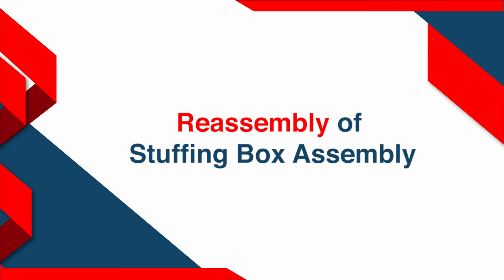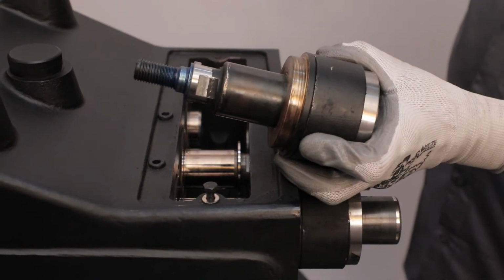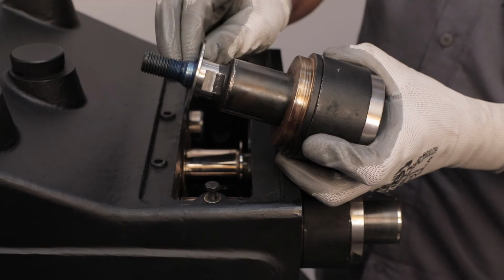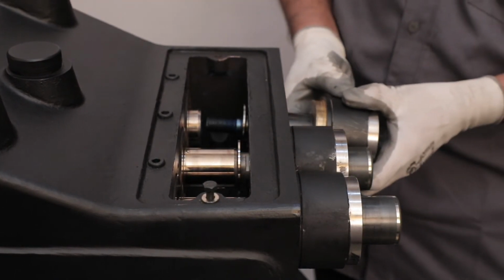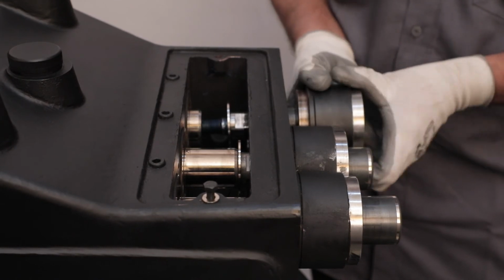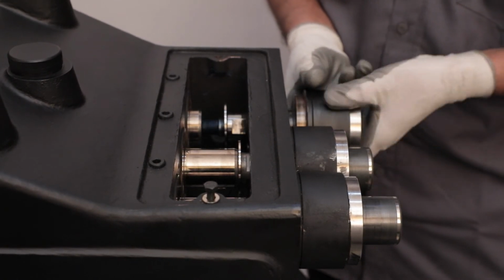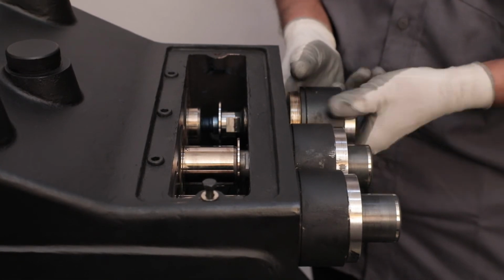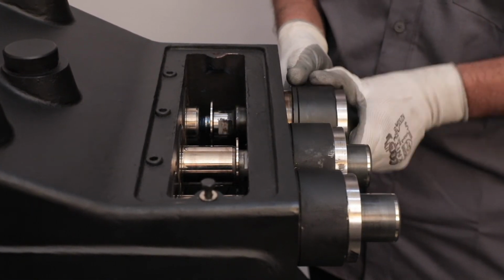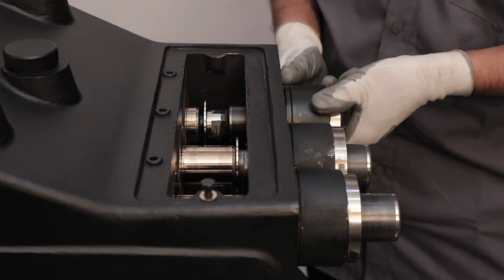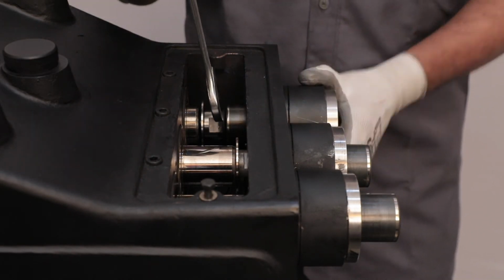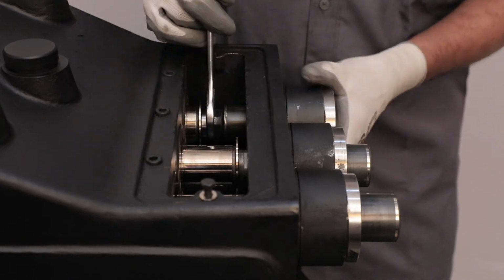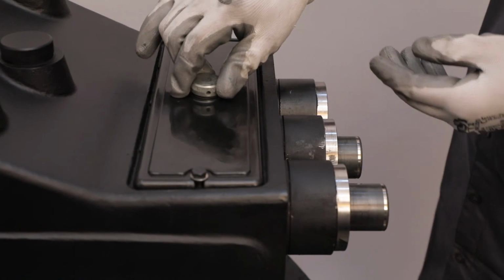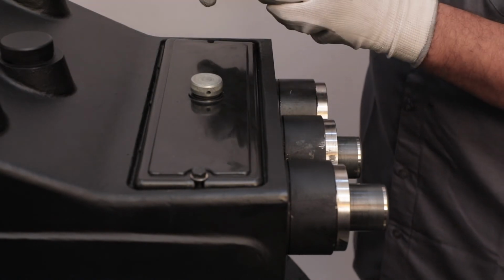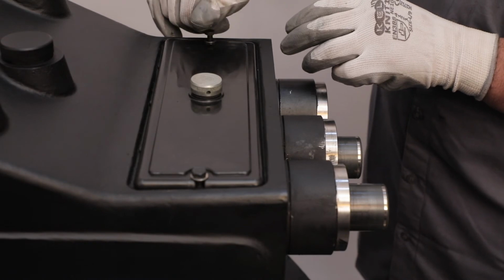Reassembly of stuffing box assembly. Put the wiper on the threaded end of the plunger. Now assemble stuffing box assembly into crankcase. Screw the thread of the plunger inside the crankcase. Then place plastic crankcase cover and screw M6 by 16 hex bolt and tighten it with a spanner.